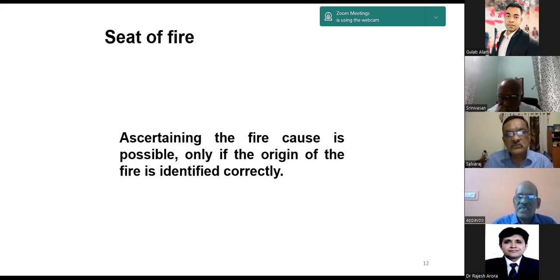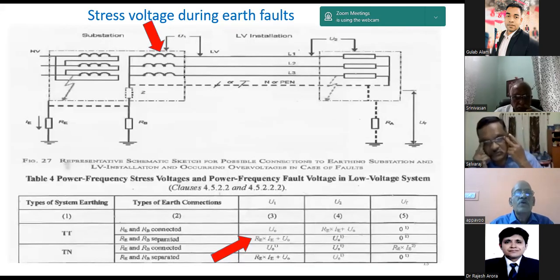It was also ascertained that there was no problem with the adjacent consumer who is around 1.5 to 2 kilometers away from this premises. None of his lightning arresters and his area was facing any lightning activity. So we ascertained that the lightning could have occurred within a radius of 1 or 1.5 kilometer from the consumer premises. In order to ascertain how the lightning transformer could fail during the lightning, we have to understand some basic things.